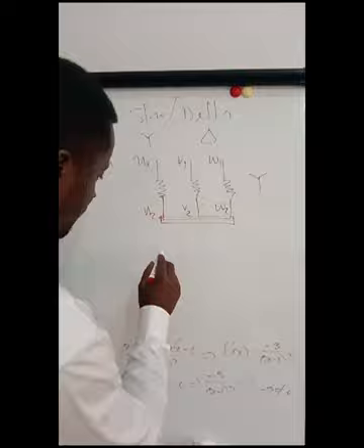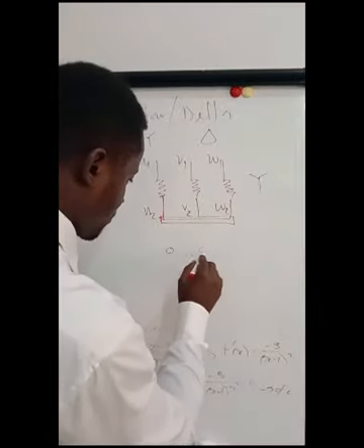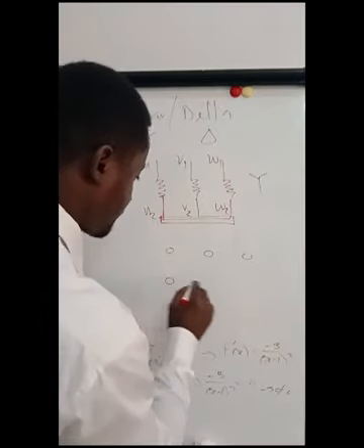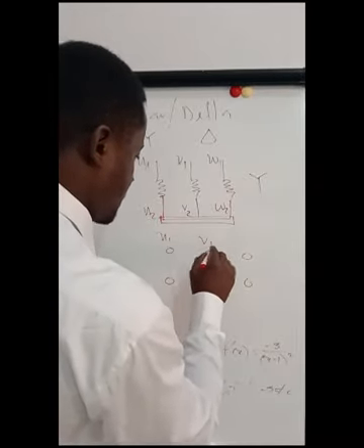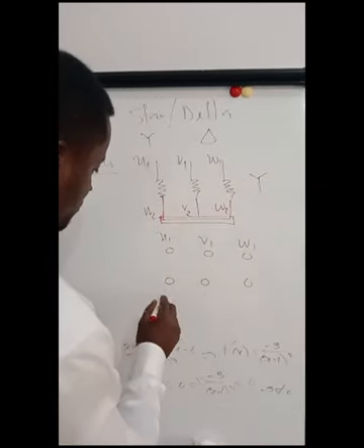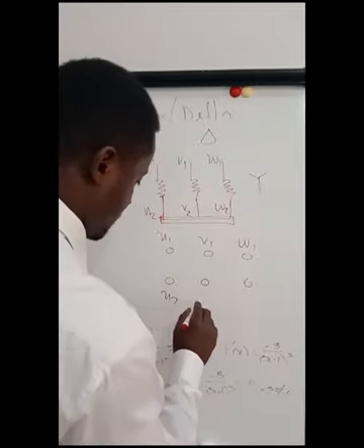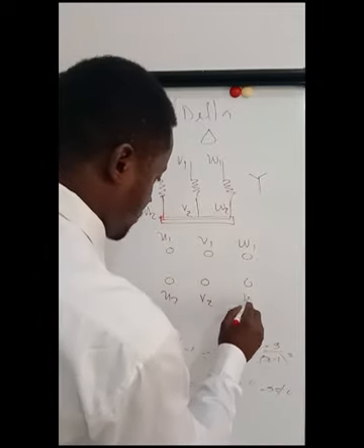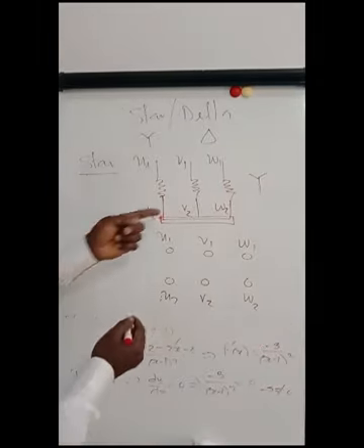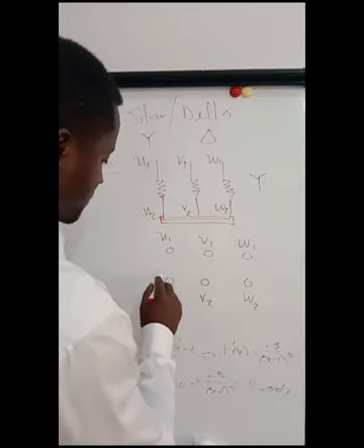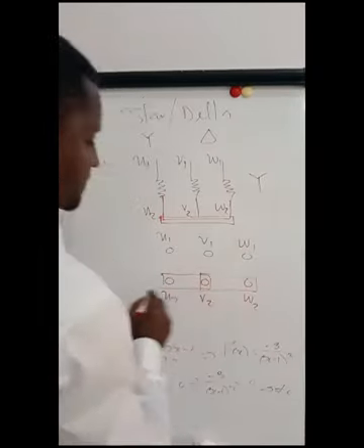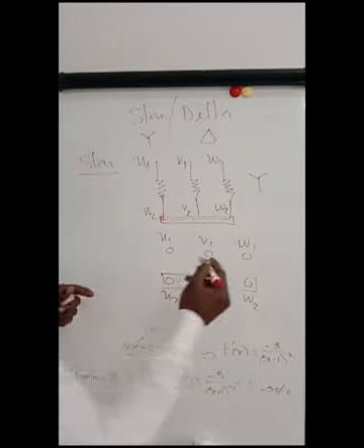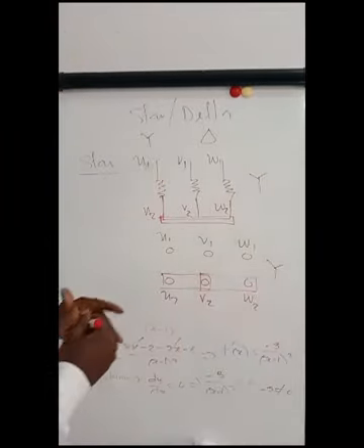The same way, if you look at your electric motor, you will see them as such. Here will be U1, V1, and W1. Here will be U2, V2, and W2. So to connect this in star, we'll connect all of these windings together. So we configure it in star.